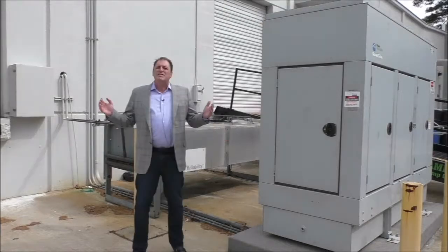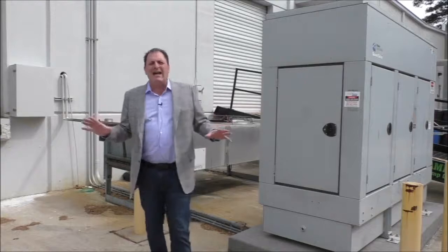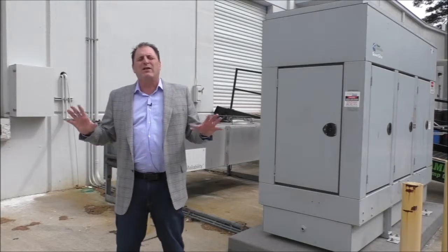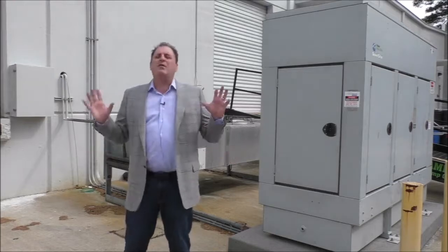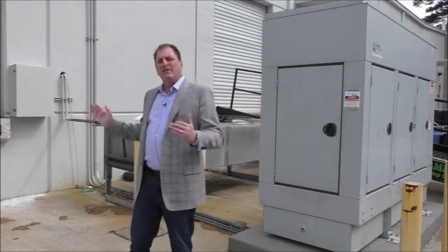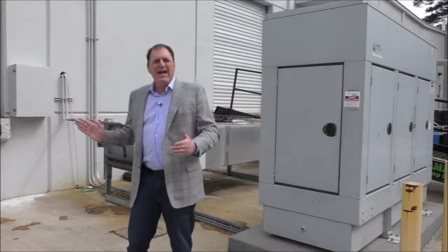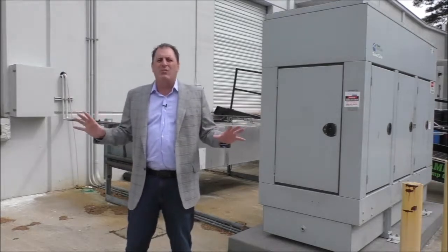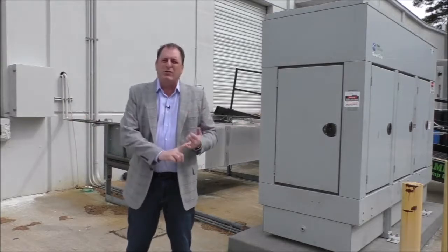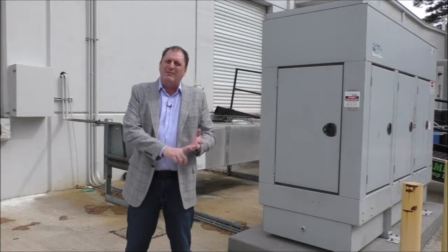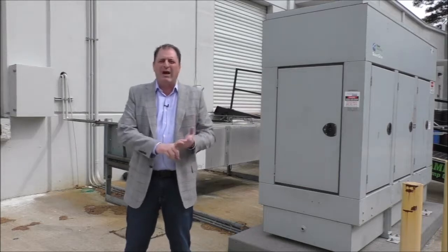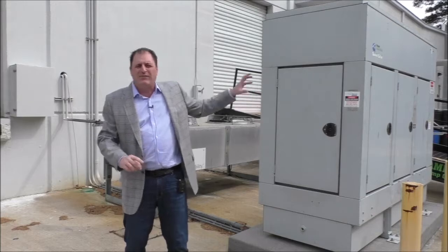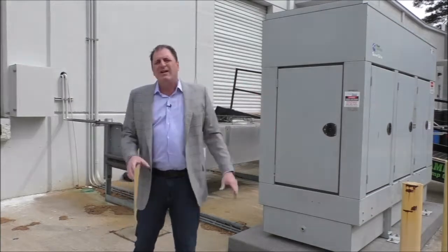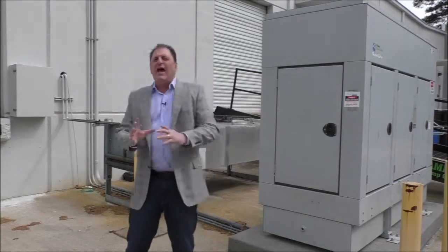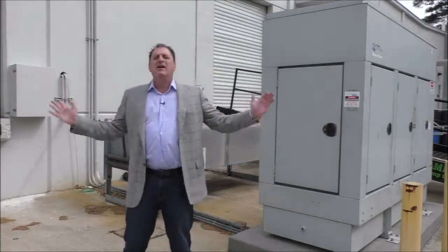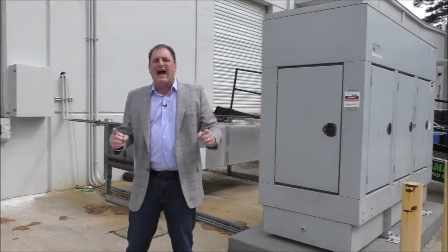There we go. So after that delay, the generator has come on and is powering our data center. But had we not had the UPS, every single one of our servers would have shut down. It's not a matter of them coming immediately back on when there's power—they lose whatever they were doing when they shut down, and they take time to come back up and have to be reprogrammed. So while this generator can keep me going for several days if needed, if I had lost that 10 seconds, everybody in my data center would be scrambling, and you would have trouble surfing the web right now.